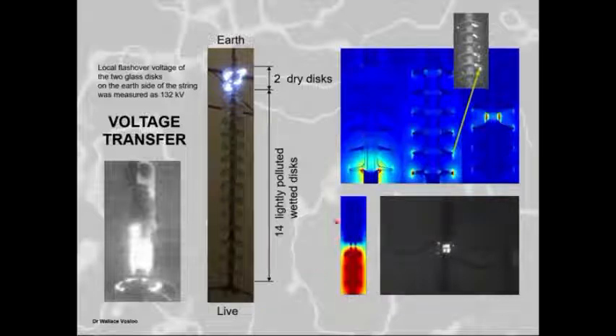Here, to give you an idea of fields, is that little insulator I showed you. Here's the live side, there's the dead end side, and it's fully polluted from live to dead end. And this is a clean one, sorry, this is a clean one. And on the clean one, you can see the stresses are sitting at the actual hardware. And this one is evenly polluted from live to dead end. And you can see that the actual stresses are now sitting in the areas of smallest curvature, which is the shed tips. And this is what I took with the Corona camera I designed. I designed the world's first daylight Corona camera along with the CSIR. And these were some of the results of the older camera we designed, the night camera.